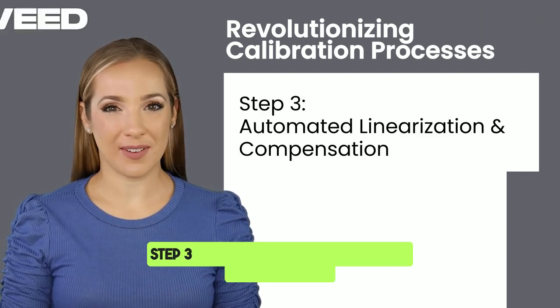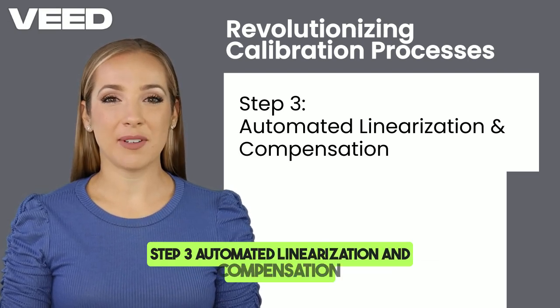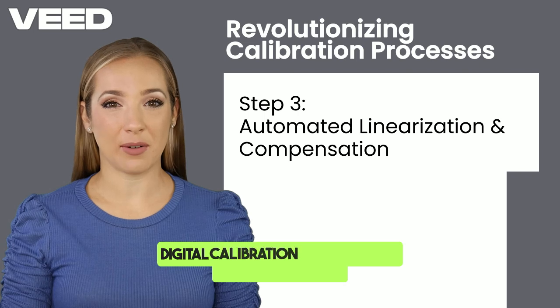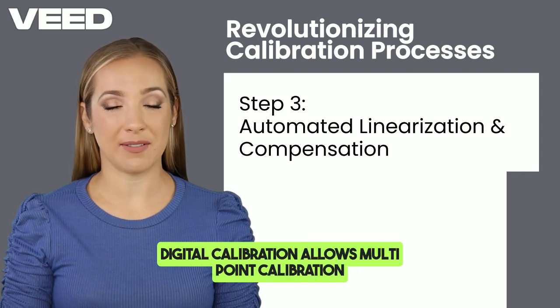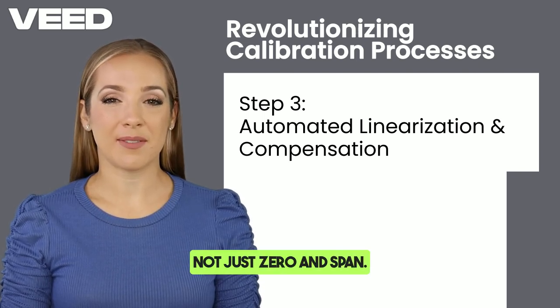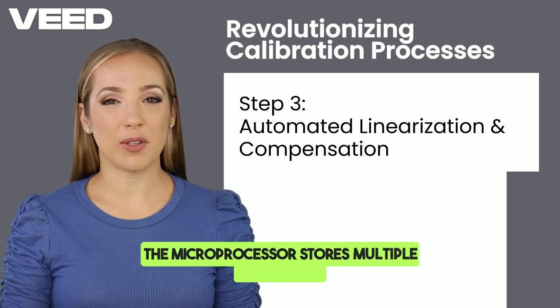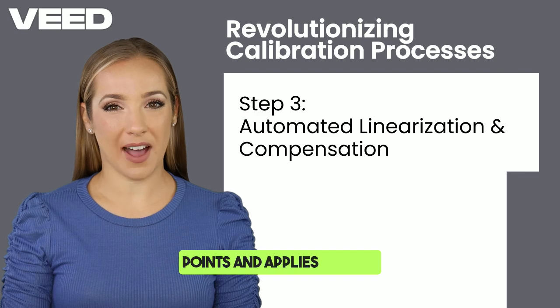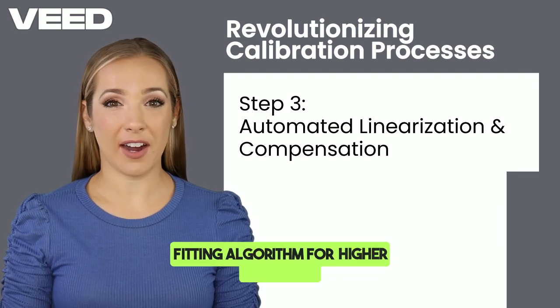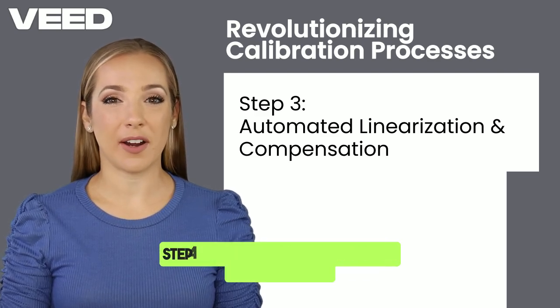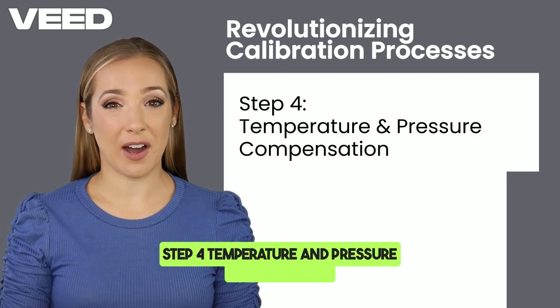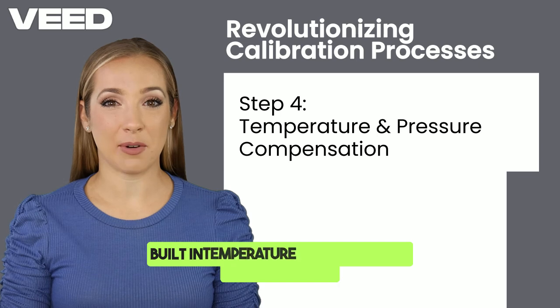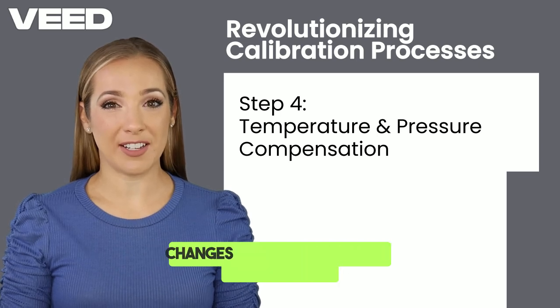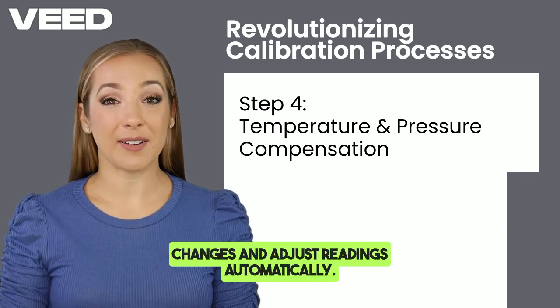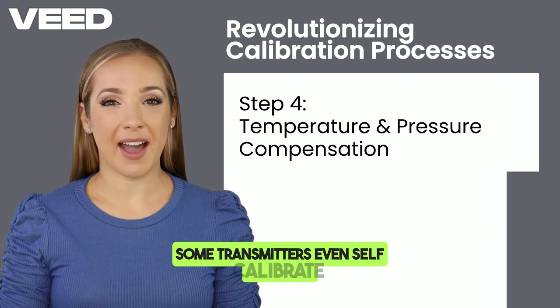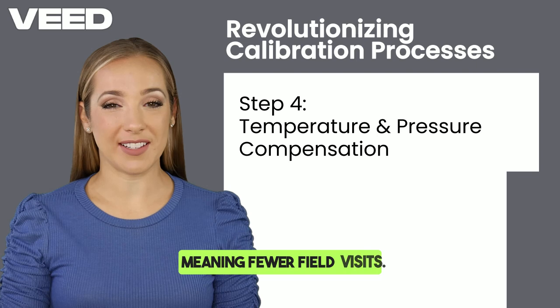Step 3. Automated linearization and compensation. Digital calibration allows multi-point calibration, not just zero and span. The microprocessor stores multiple calibration points and applies a curve-fitting algorithm for higher accuracy. Step 4. Temperature and pressure compensation. Built-in temperature sensors detect environmental changes and adjust readings automatically. Some transmitters even self-calibrate, meaning fewer field visits.